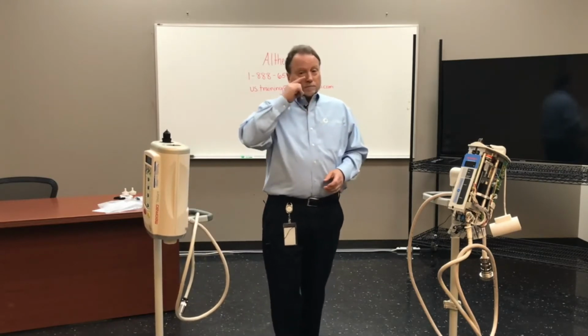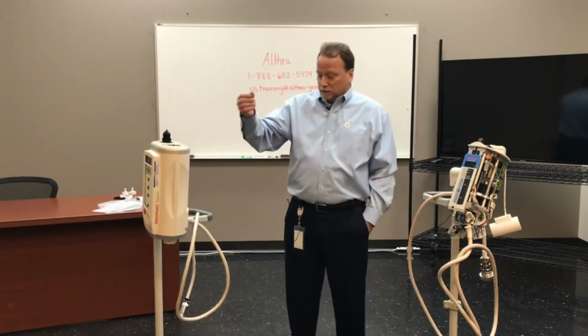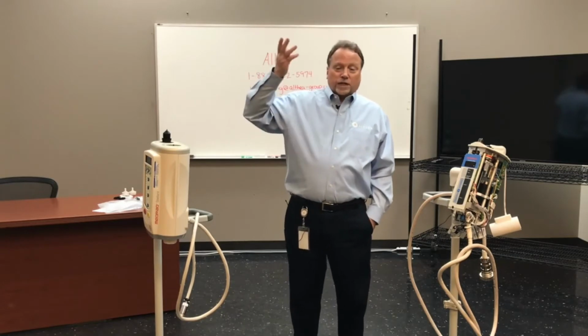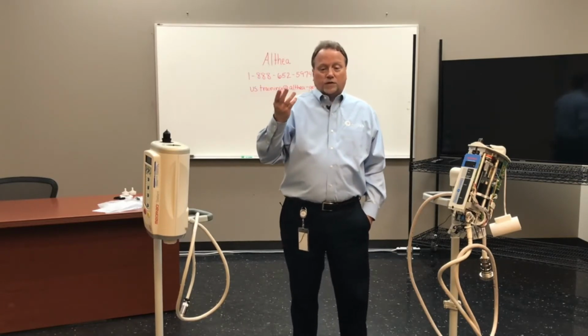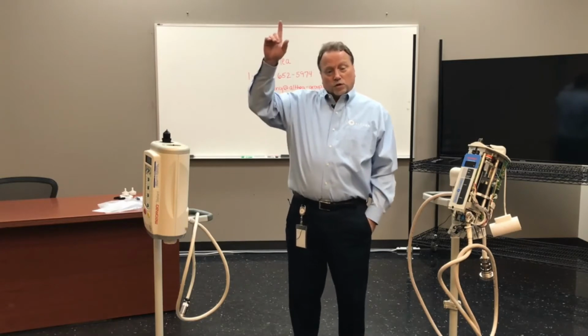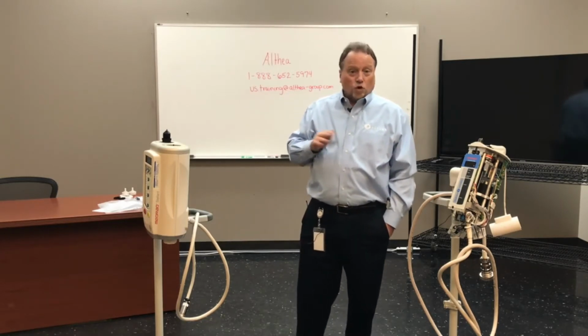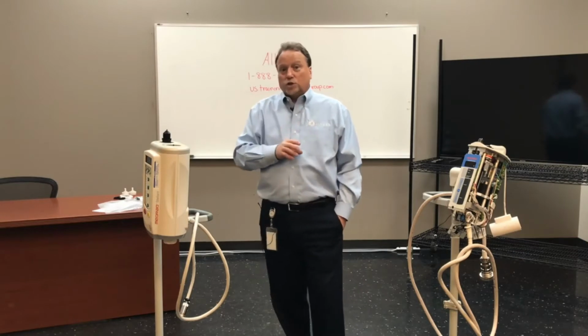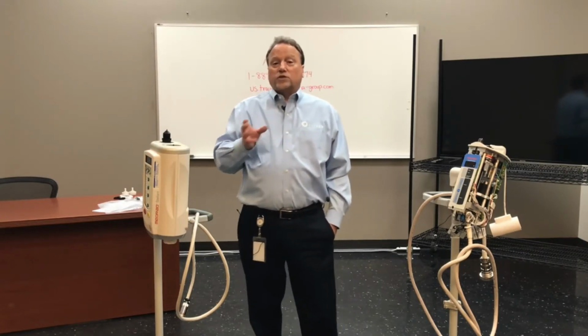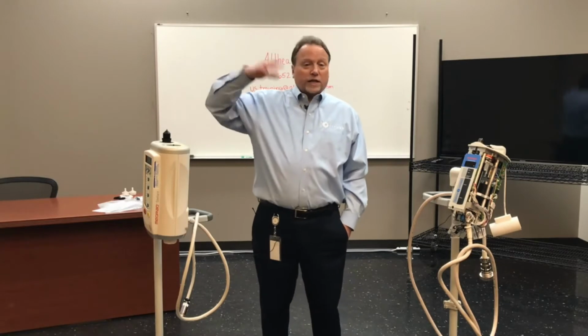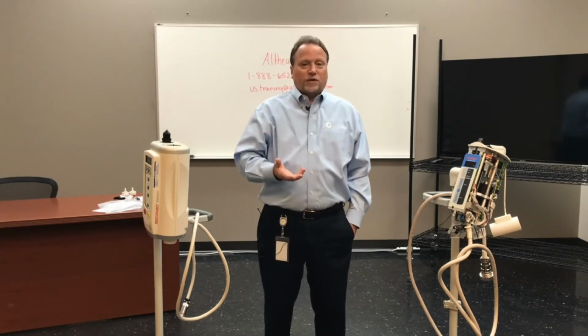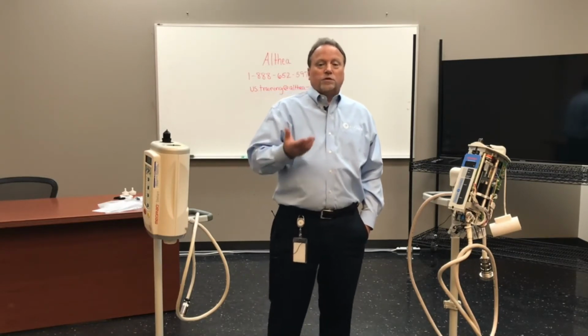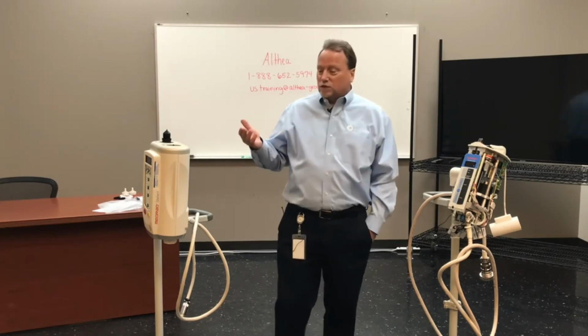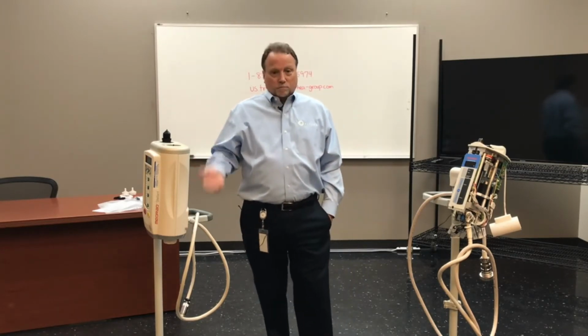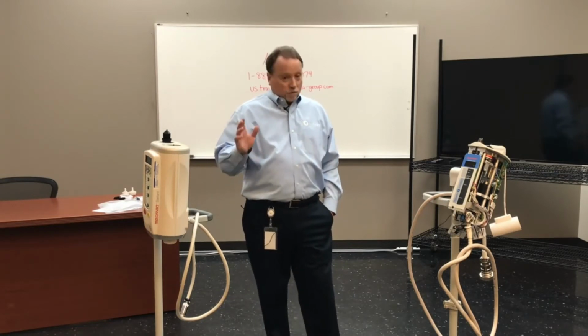So do a once-over. Inspect it. Counterpoise assembly, that's another one. If the injector is hanging from the ceiling, who does the stuff above the ceiling tiles? Normally it's facilities, but maybe it's you. So you want to make sure that is secure. Even before doing the PM, if it's hanging down, loose, whatever, that has to be fixed. That has to be resolved. Do not put yourself in danger if this injector is not safe to work on. Take it down. When I say take it down, do not let anyone use it till those safety issues are resolved.